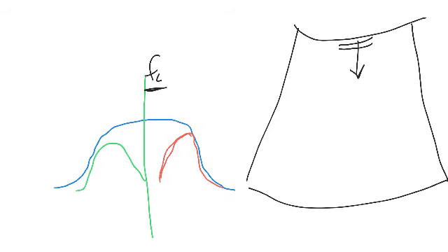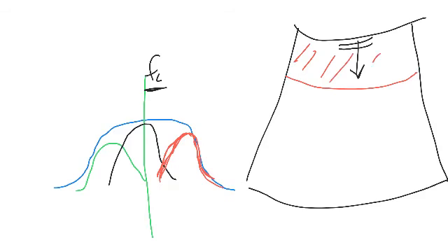Okay, so even though we say we're scanning at, say, 5 megahertz, some of these frequencies are higher, up to maybe 8, and some are lower, down to maybe 3 or 2, whatever. But it makes use of this fact, and so anything in the near field is automatically processed utilizing these high frequencies in the broadband, so that all this area is all high frequency pulse.